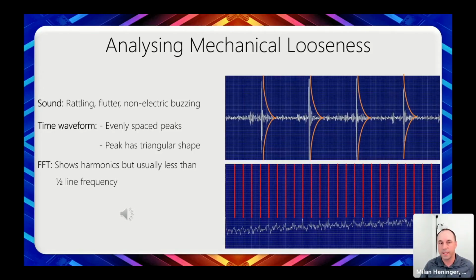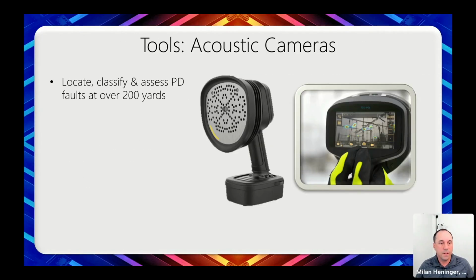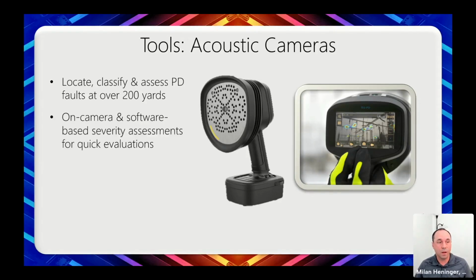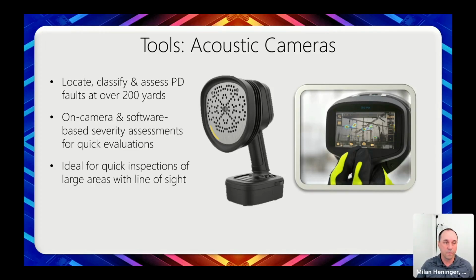The first one is the acoustic cameras. These can be very useful to locate and classify a variety of forms of partial discharge. The UE Systems tool is useful for over 200 yards away. It gives you some on-camera and software-based severity assessments for a quick evaluation, so when you're out looking through a substation, you can quickly figure out where the issues are and what those severities look like. I find it ideal for quick inspections of large areas where you have line of sight.